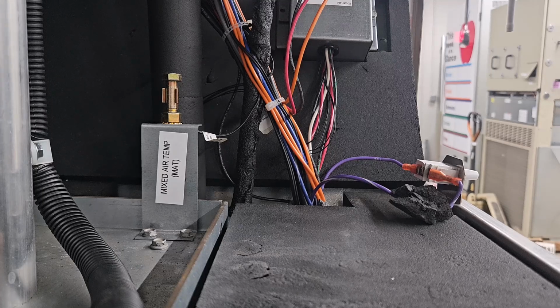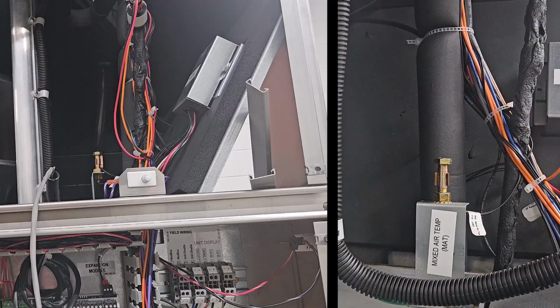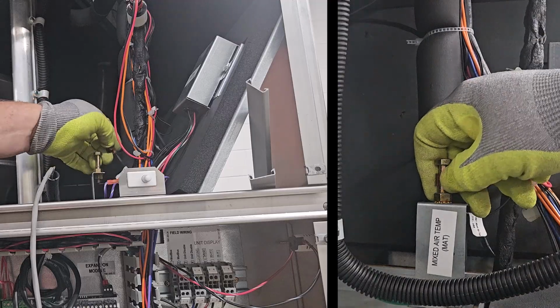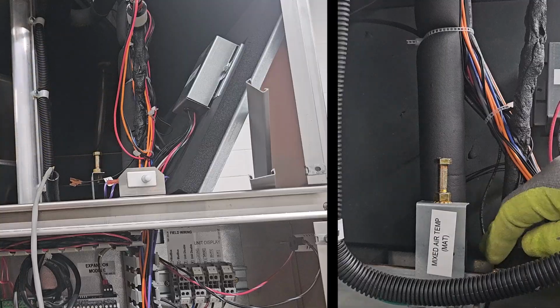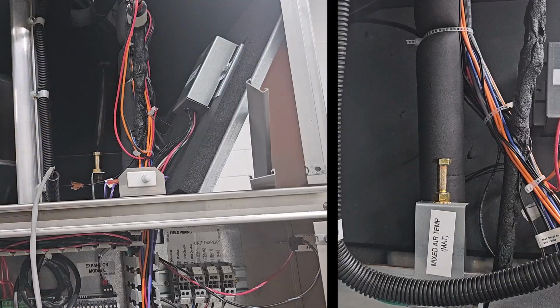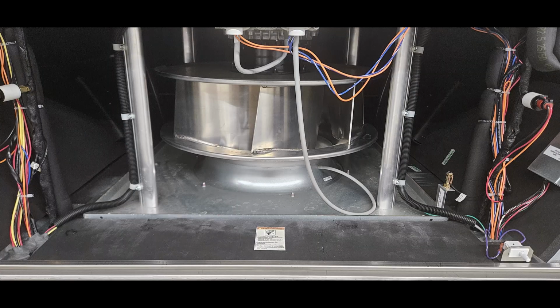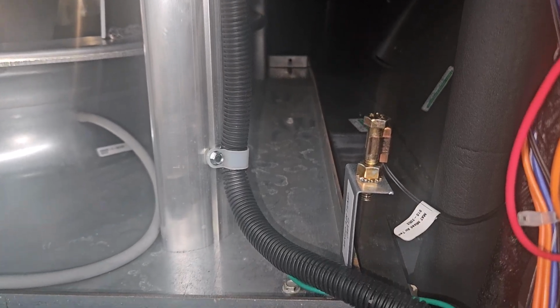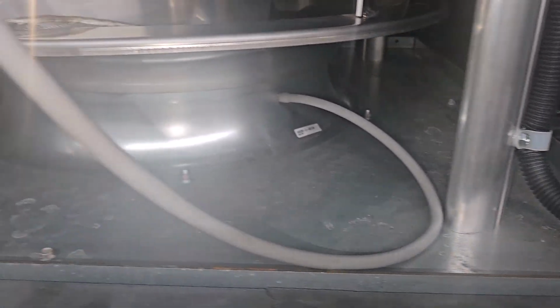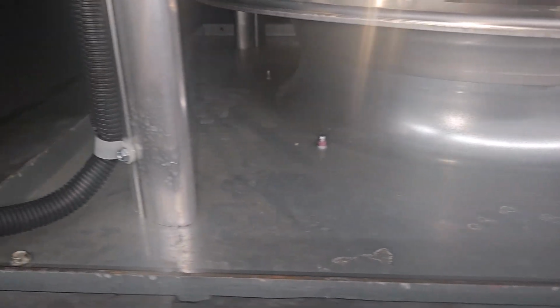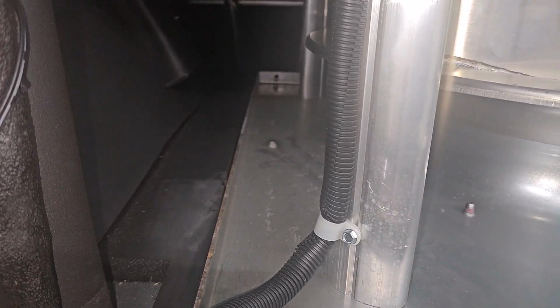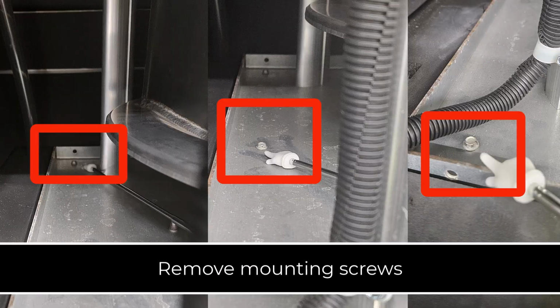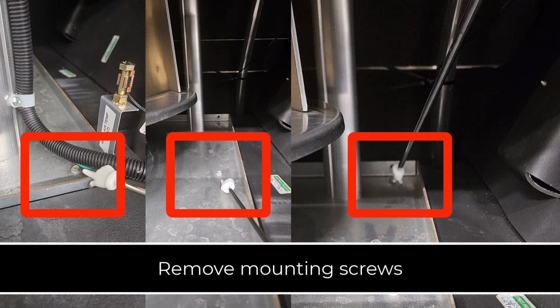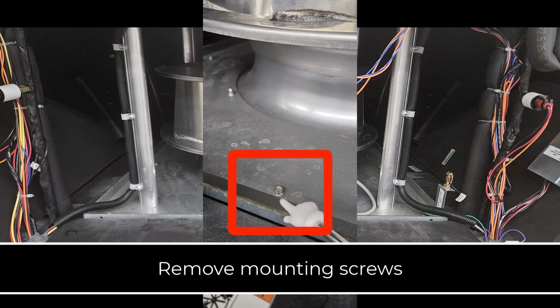Remove the mixed air temperature sensor and the mounting bracket installed onto the blower assembly. This mounting bracket will prevent you from removing the assembly from the MEGA-TEC frame. Locate the 7 mounting screws attaching the housing to the MEGA-TEC. They are located all around the assembly. Note that there is no mounting screw directly behind the blower assembly. They are right, left, and front middle.